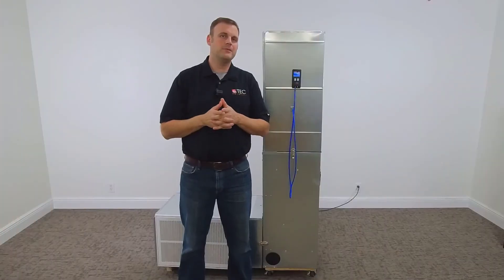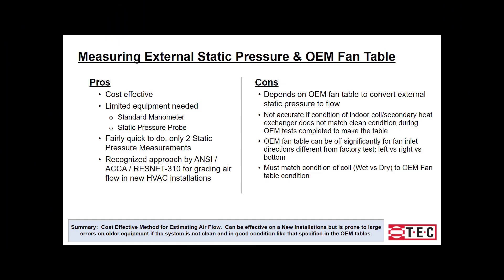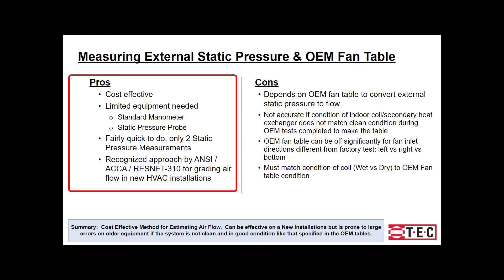Let's get into the pros and cons of the total external static pressure method. Starting with the pros: this method is cost effective and the equipment needed is minimal. It's a fairly quick method to accomplish, and it's recognized by ANSI, ACCA, and RESNET-310 for grading airflow in new HVAC installations.